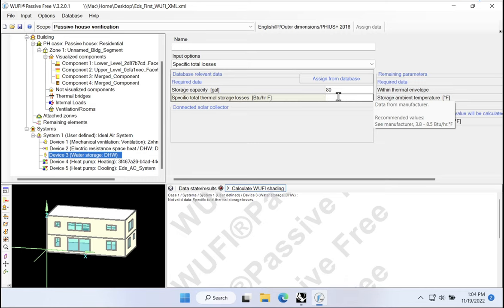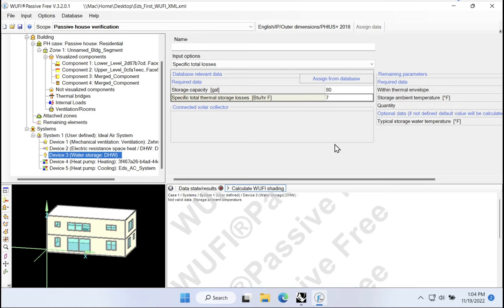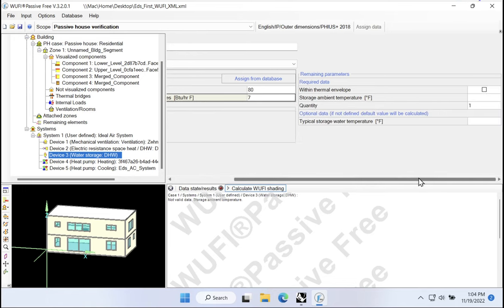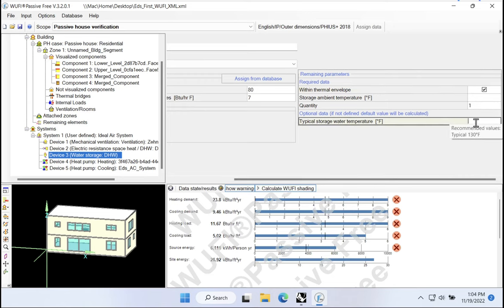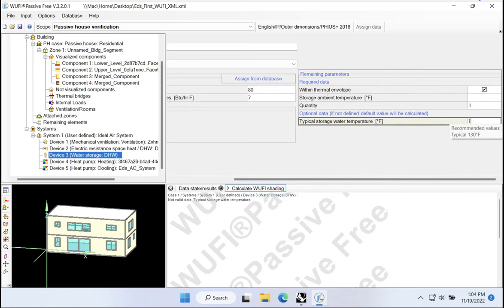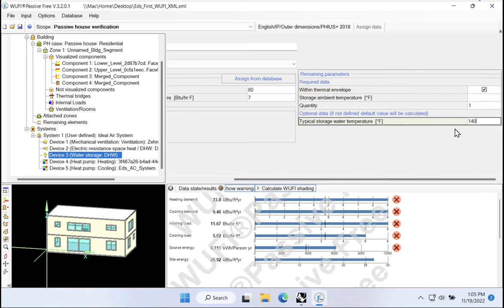So I could come over here and I would come down to water storage. And in water storage, I would properly set it up. So maybe it's an 80 gallon tank. Of course, the tank thermal storage losses, BTUs per hour degree Fahrenheit, is not a number that you'll ever know. That's like a number for European specified equipment. So you're not going to get that for North American equipment. So let's just put in like a seven or something like that, like a conservative value there.